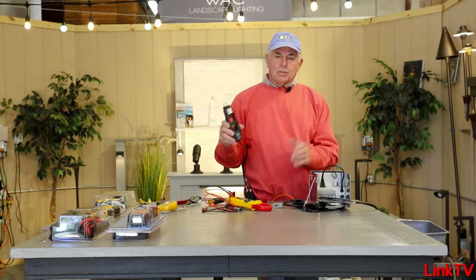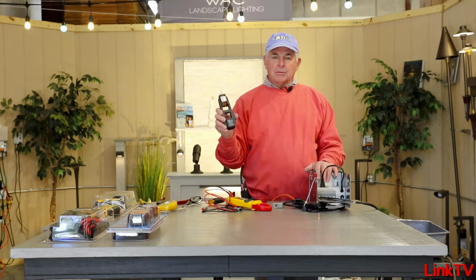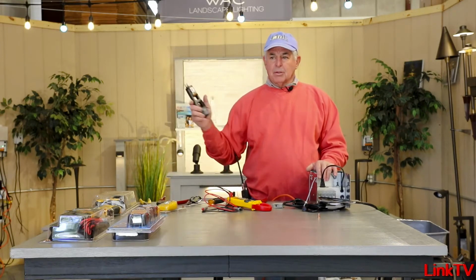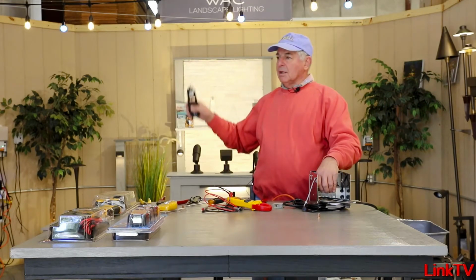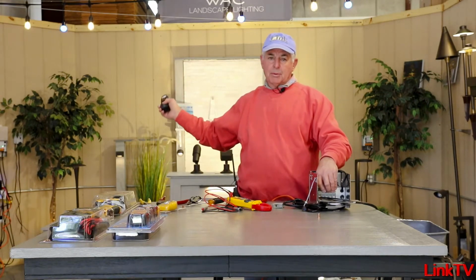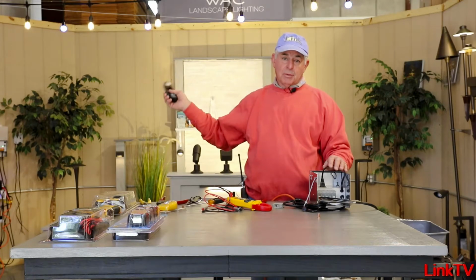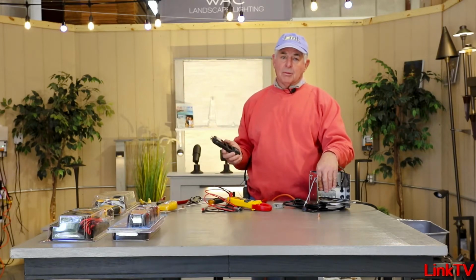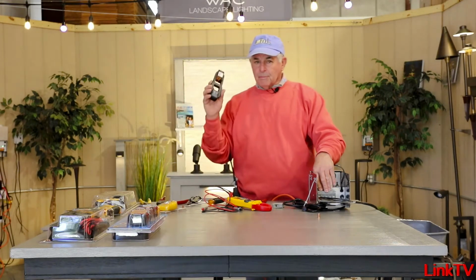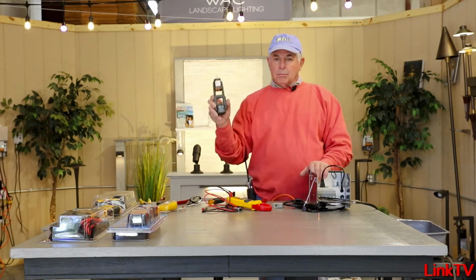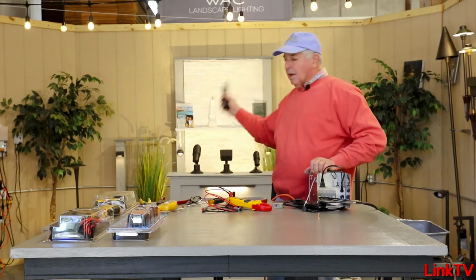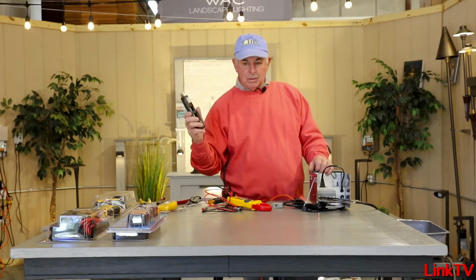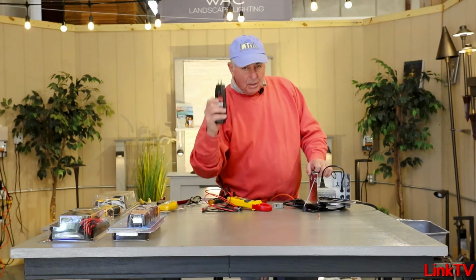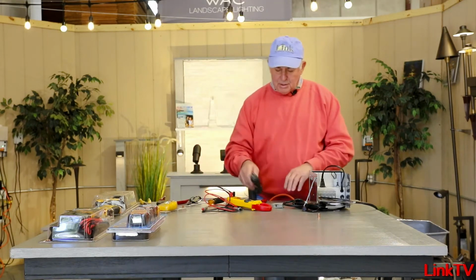All it can do is take what you put in it, factor it by 10, and put it out. So if it's low on the secondary side, it's probably low at the receptacle, and vice versa. If it's high at the receptacle, it's going to be high on the secondary side. So when you're doing an install, one of the first things you need to do is find out what your primary voltage really is.